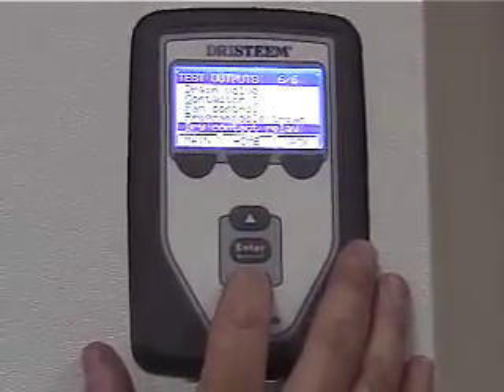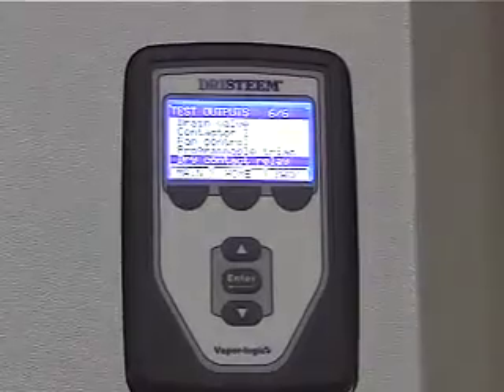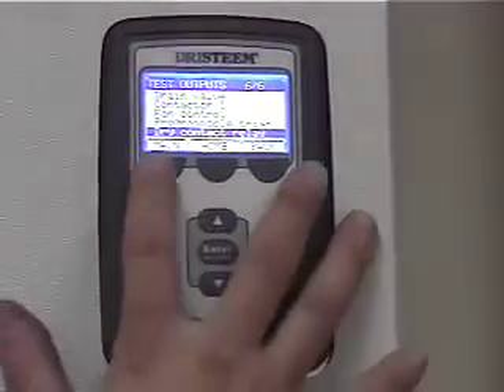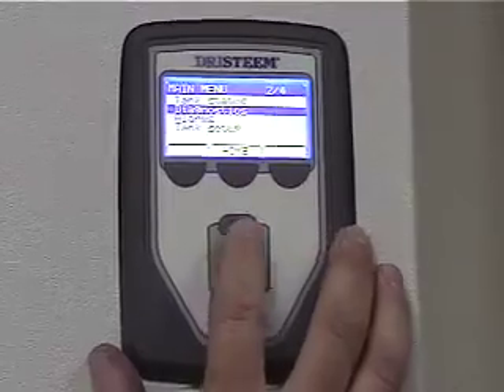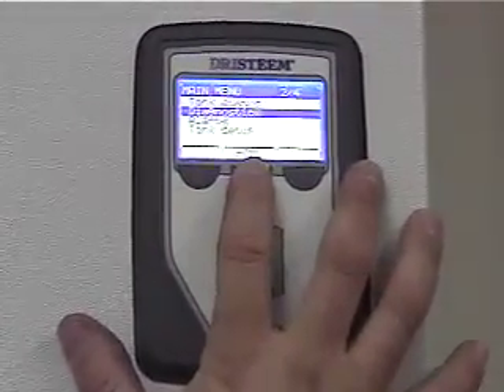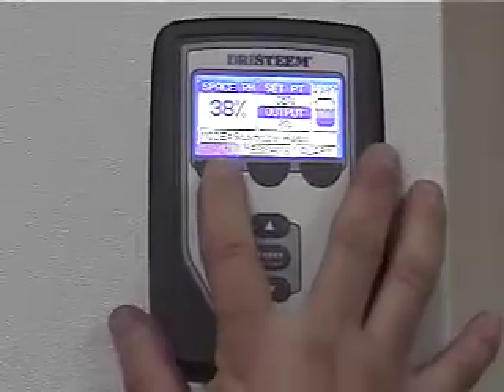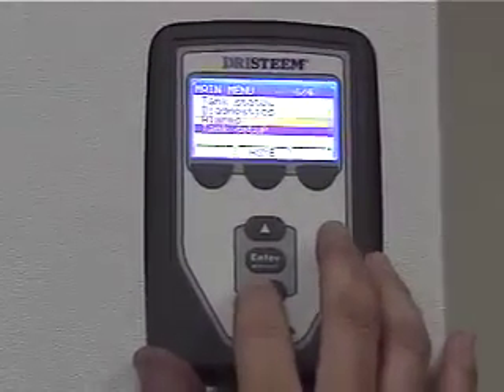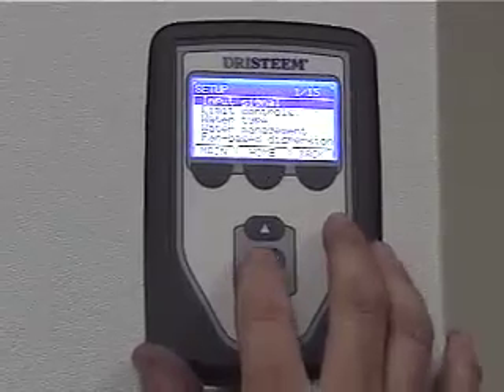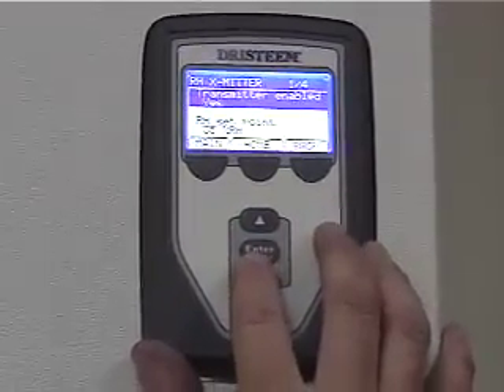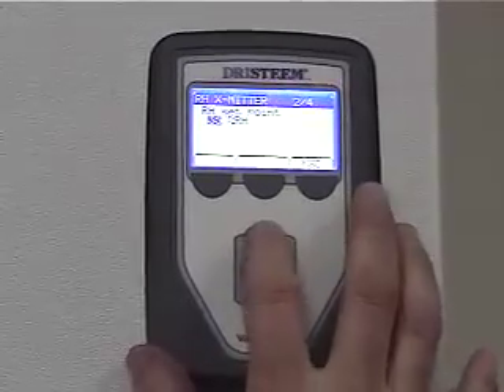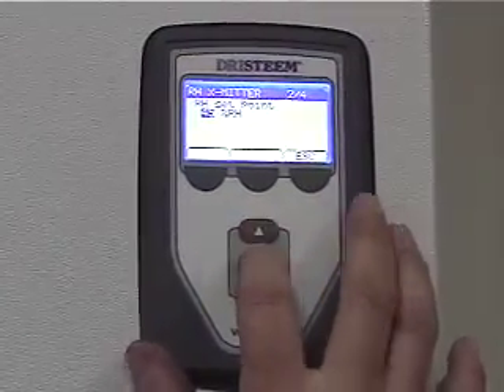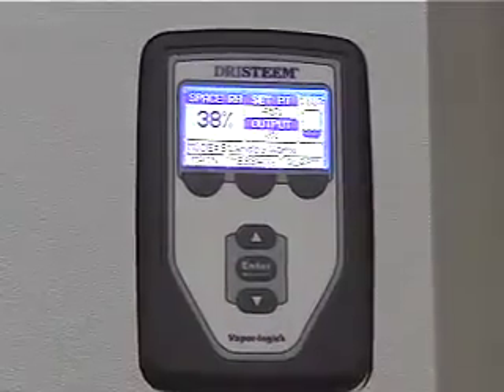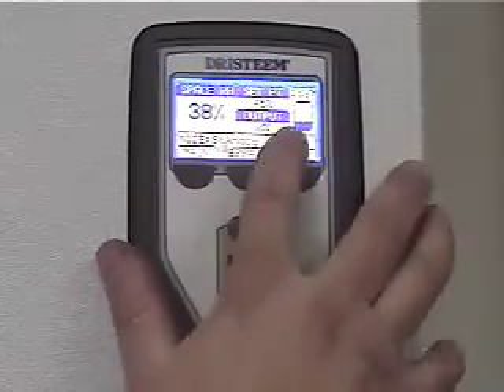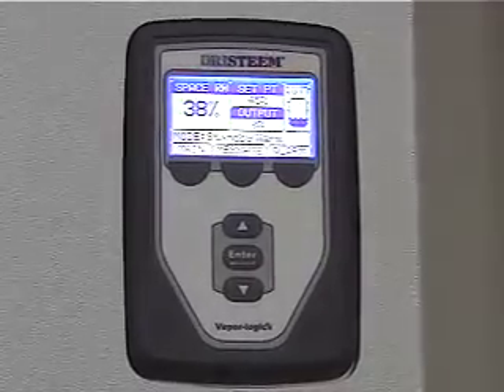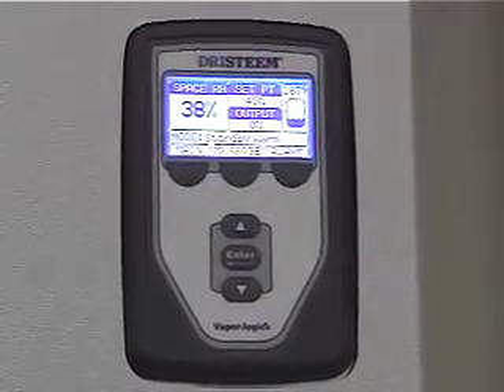Our dry contact relay would be our alarm output, to know if we have an alarm coming out of this thing or not. Let me see if I can get in here and change our set point. So I just changed our set point up to 45 degrees. You can see our water level. I dropped it when I opened the drain.